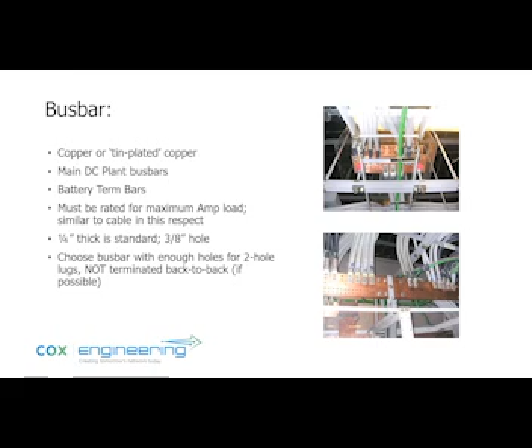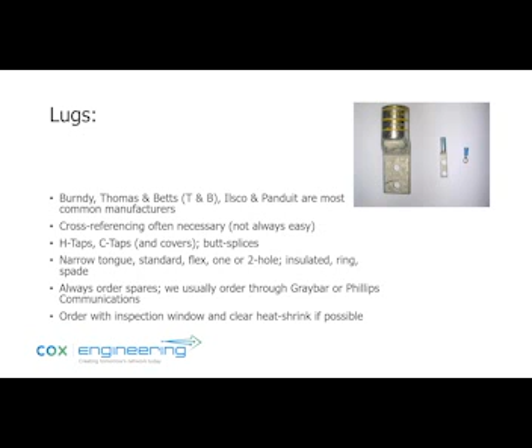lugs. Burndy, T&B, ILSCO, Panduit. You have your larger ones, you have your smaller ones that go to the equipment. You have narrow tongue, insulated, ring, spade, 1 or 2 hole. Always want to order spares. You want to order them with an inspection window and clear heat shrink if possible. That's how we are able to see if you are actually crimping them properly.